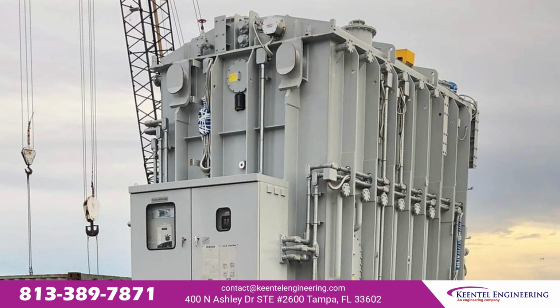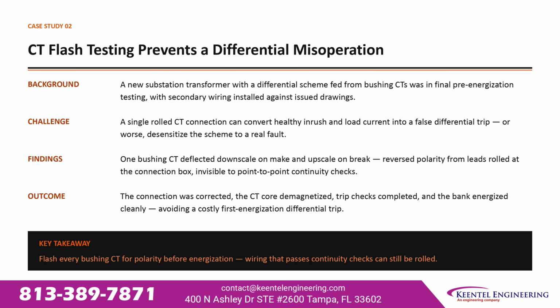A new substation transformer with a differential scheme fed from bushing CTs was in final pre-energization testing, with secondary wiring installed against the issued drawings. The risk: a single rolled CT connection can convert healthy inrush and load current into a false differential trip, or worse, desensitize the scheme to a real fault.